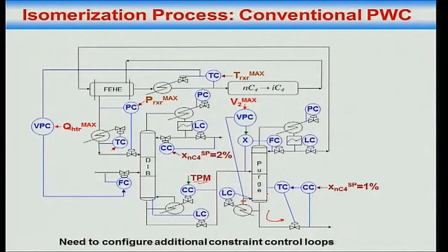As long as this loop is working, there will be an increase in boil up. Yes or no? Right. So as I increase the reflux, boil up will also increase. Yes or no? Okay. But I don't want the boil up to hit max, because I don't want to lose control of what's leaking down, because there is an economic penalty associated with that.